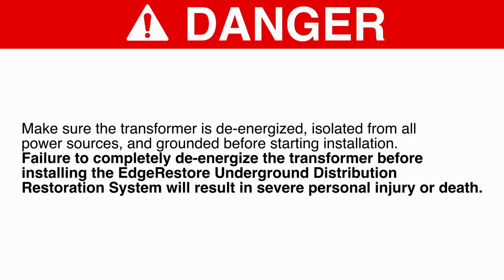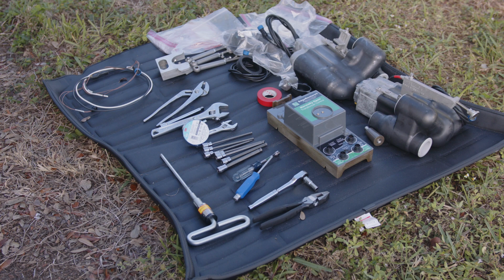Danger: make sure the transformer is de-energized, isolated from all power sources, and grounded before starting installation. Failure to completely de-energize the transformer before installing the EdgeRestore underground distribution restoration system will result in severe personal injury or death. Tools are not provided by S&C Electric Company.